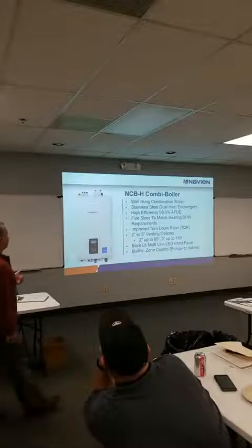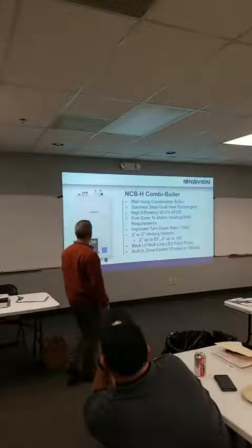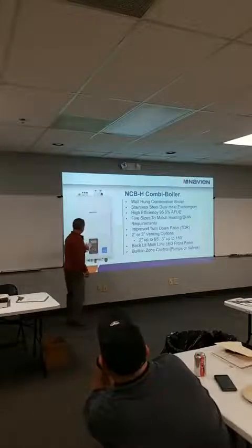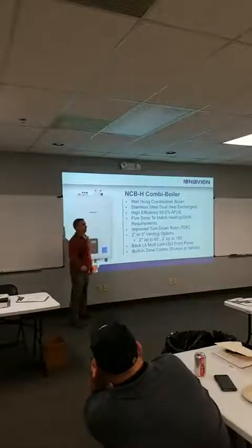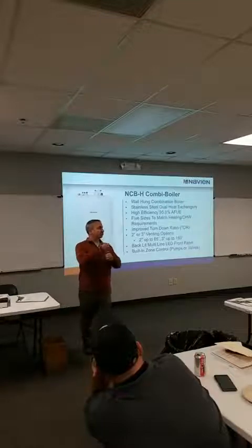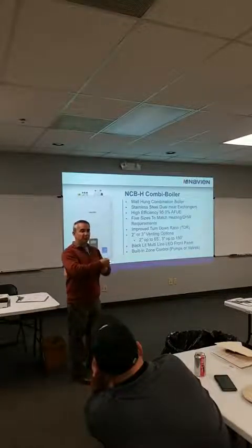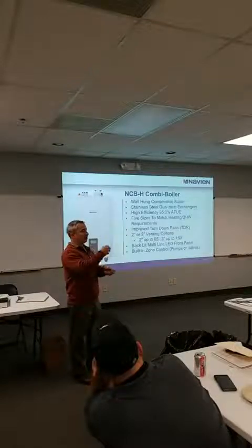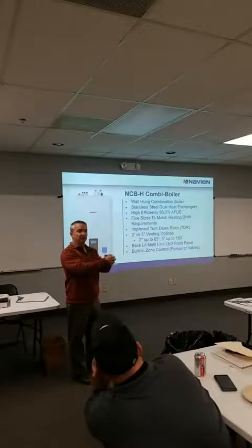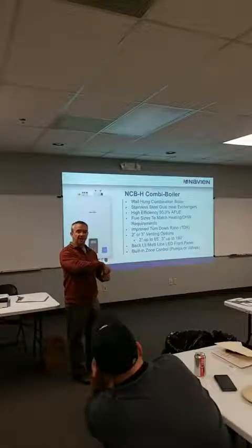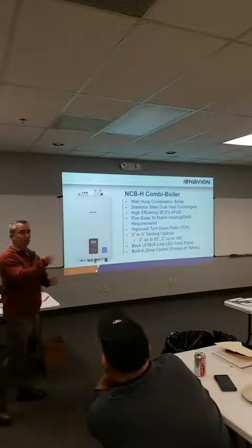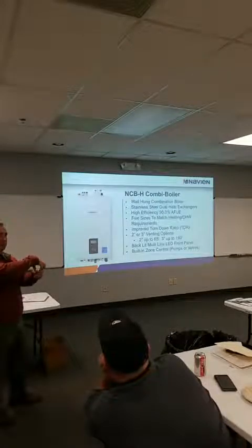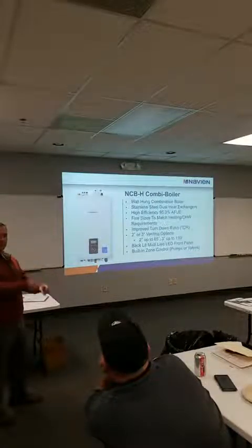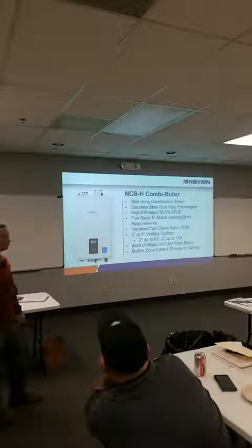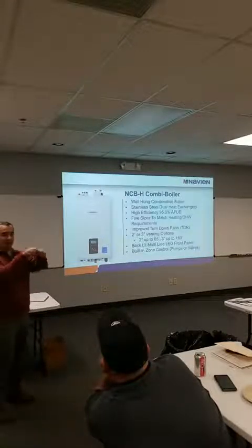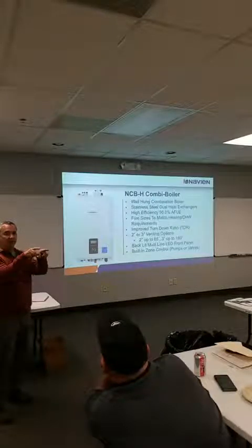This H model is the upgrade model. So basically, we put the new keypad on it. We put in this new vent installation detector, and that's going to be on all of our new equipment. So if you don't slide your vent pipe all the way down and seat it properly, the unit will not fire. We have people trying to use street elbows and they don't go down far enough, or just getting the pipe through the top gasket, not to the bottom gasket. So this pipe has to go down a solid 3 inches, sealing on the burner assembly gasket. There's a switch down there? Yes, a safety switch in there now. If you don't get all the way down, CO can leach out over that gasket and into the unit itself.